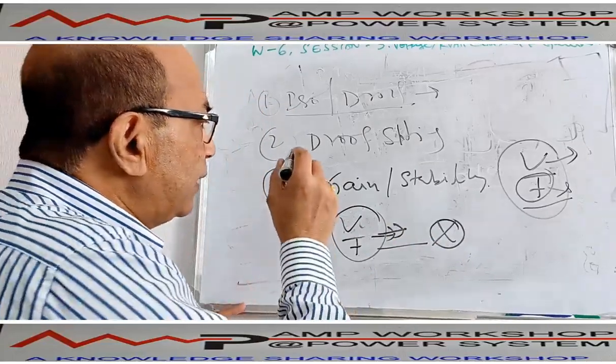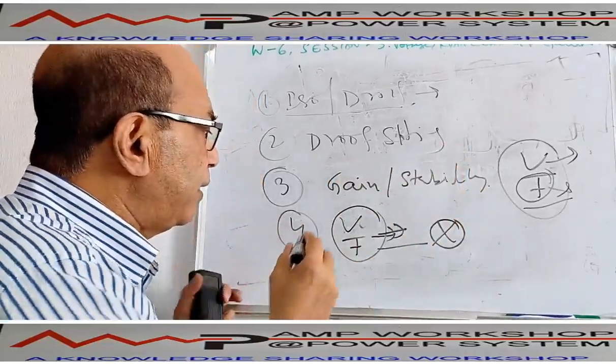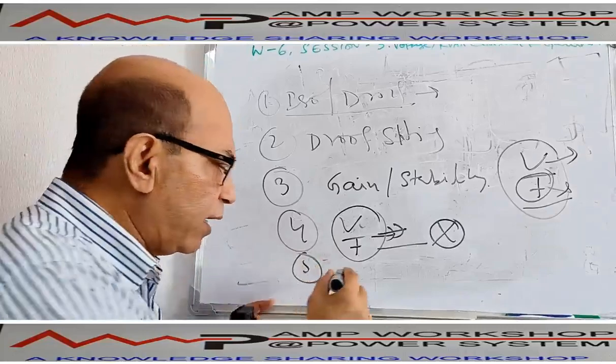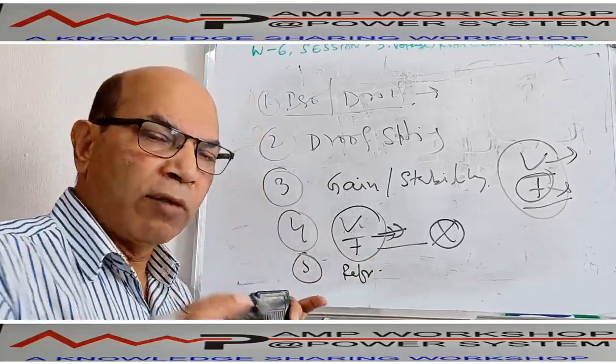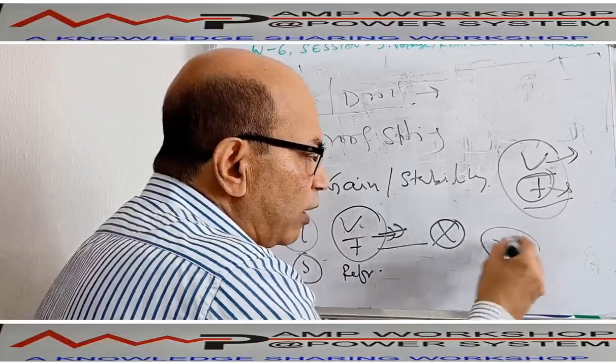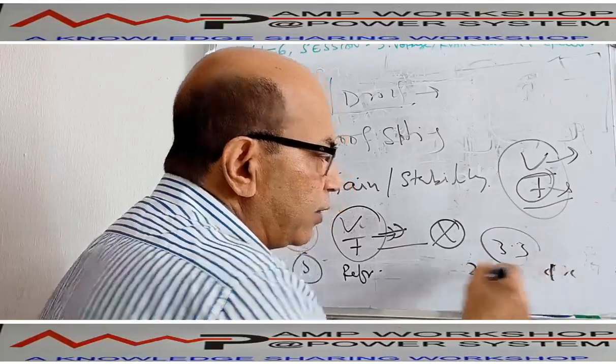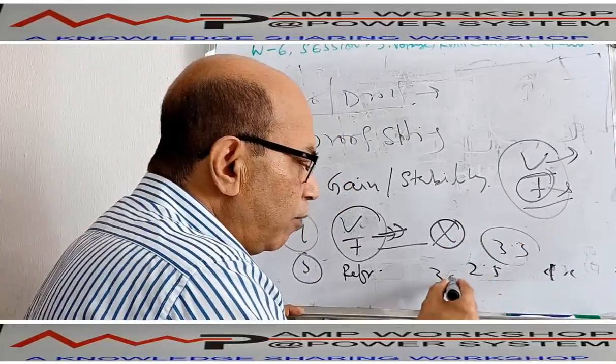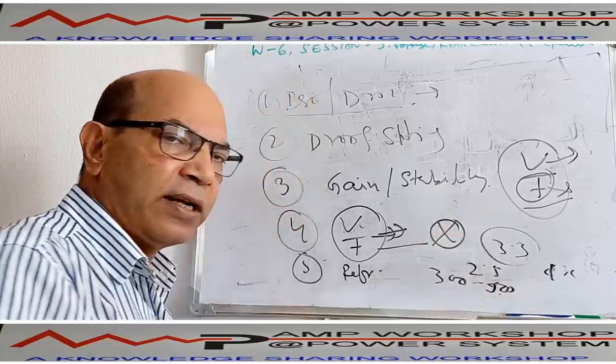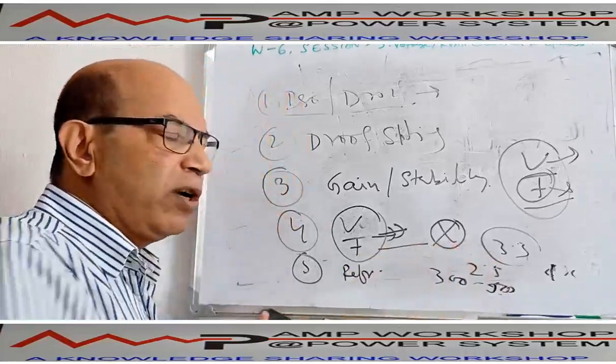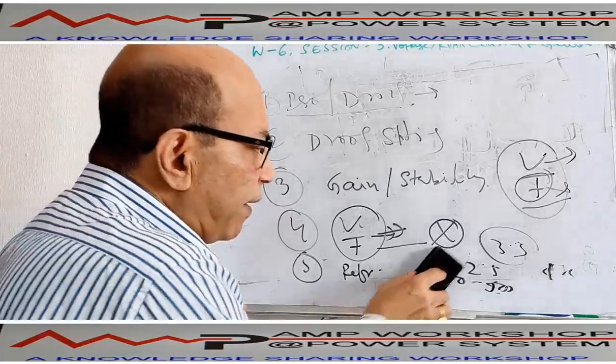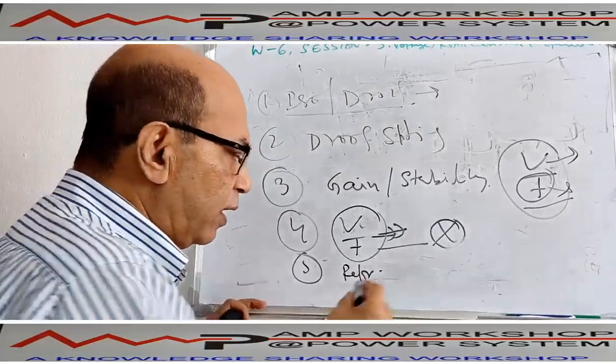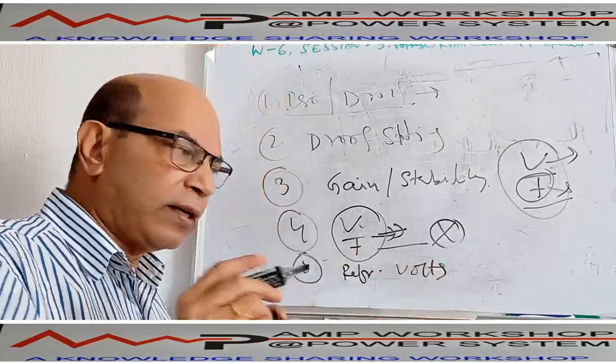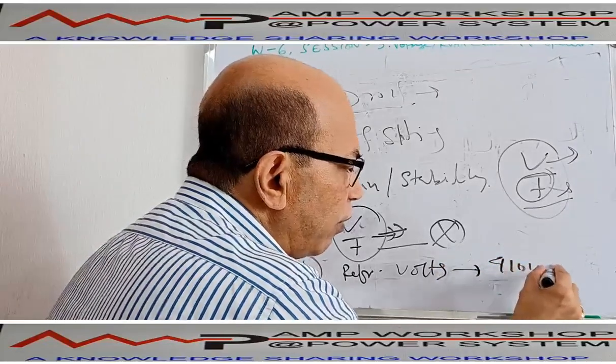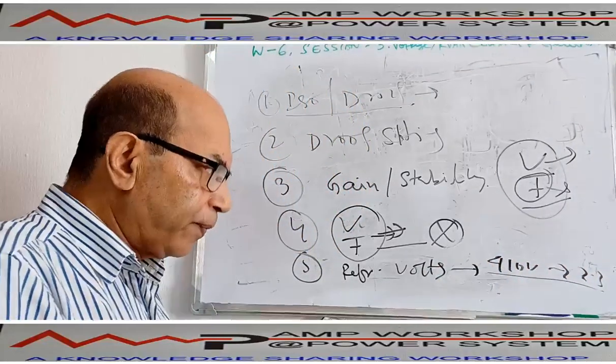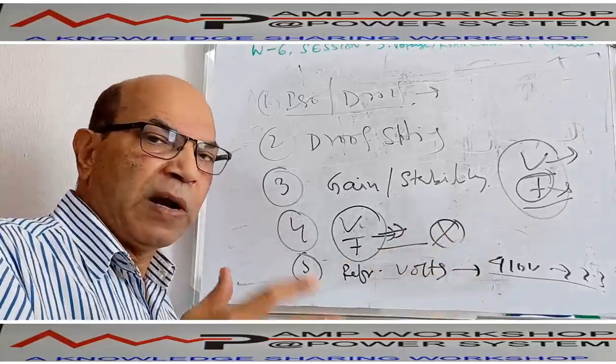In addition to this, the voltage setting which we are giving, and the fifth switch, is the reference voltage setting. We are giving the reference voltage. Now for the reference voltage setting, normally, if it is a 3.3 kV machine, the reference voltage setting is available from 2.5 kV to 4 kV like this. In terms of secondary, it will be maybe 300 volt to 500 volt, PT secondary voltage. So at what voltage you have to set, one switch is required. That is called the reference voltage setting or volt setting. We call it the volt setting switch. Now once we put the voltage, suppose you put 410 volt, which is equivalent to 3.3 kV, then this voltage again can be changed because there is a variation.